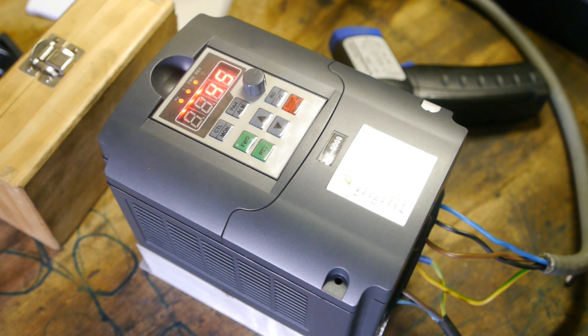Perhaps this model was meant to be installed into a cabinet, but I don't think that is mentioned anywhere in the user manual. By the way, I've asked the manufacturer about the missing ground terminal. Their response: not all single phase models need a ground terminal. That's it, no more explanation. I don't think this will do on the European market.